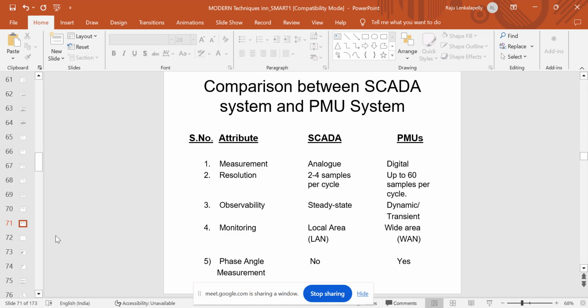SCADA measures only 2 to 4 samples per cycle. A cycle is 20 milliseconds, since in India we have 50 hertz frequency. Whereas PMU measures up to 60 samples per cycle, depending on the hardware. In terms of observability, SCADA is steady state, whereas PMU is dynamic in nature.